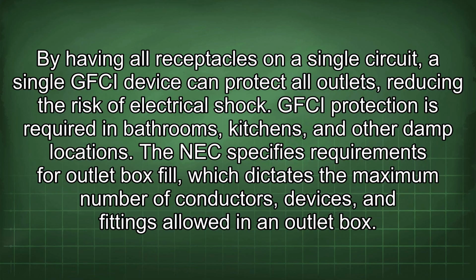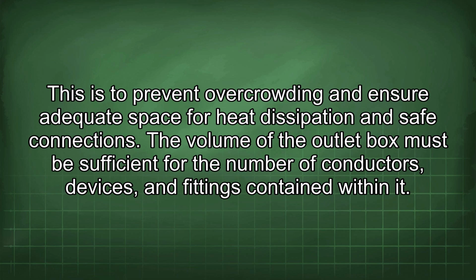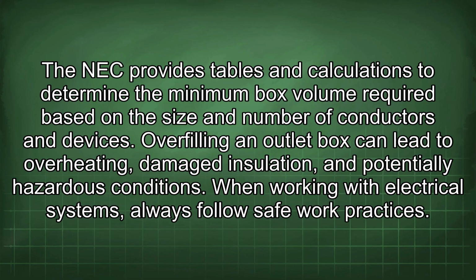The NEC specifies requirements for outlet box fill, which dictates the maximum number of conductors, devices, and fittings allowed in an outlet box. This is to prevent overcrowding and ensure adequate space for heat dissipation and safe connections. The volume of the outlet box must be sufficient for the number of conductors, devices, and fittings contained within it. The NEC provides tables and calculations to determine the minimum box volume required based on the size and number of conductors and devices. Overfilling an outlet box can lead to overheating, damaged insulation, and potentially hazardous conditions.